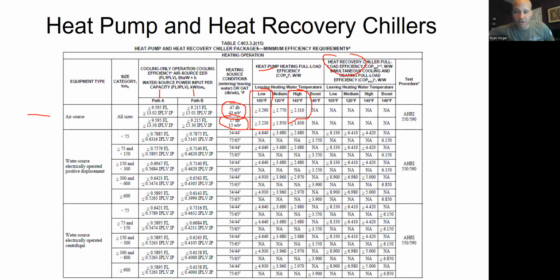I realize I just talked a bunch of stuff there and rattled it off. If you guys have questions, please ask them. And then if we were in the water source section, which I won't go through in detail, it would work the same way. The only difference on how that would work, other than me picking the tonnage, is that I would also on here tell it what water temp I'm designing for. And 44, 54 is going to be the closest one that I'm going to have. That's what the machine's going to be typically rated at anyway for most chillers.